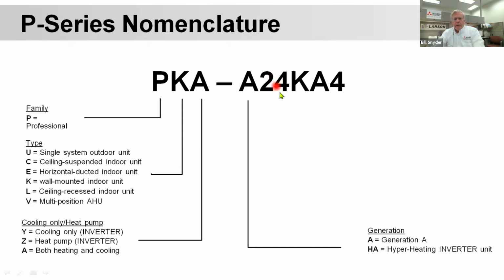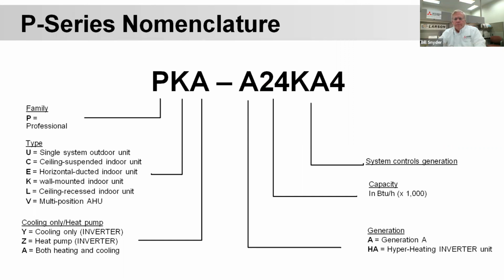Just like in the M series, the 24 is the nominal BTU capacity. I say nominal because it's not necessarily exactly 24. You go to the submittal data and you might find this is 27,000 BTUs, or it might be 22,000 BTUs, but it's a nominal 2-ton. So just be careful of that when you're selecting equipment, just like the American products that we sell. The system controls sequence is similar to what the M series was, and the last digit is a model version.